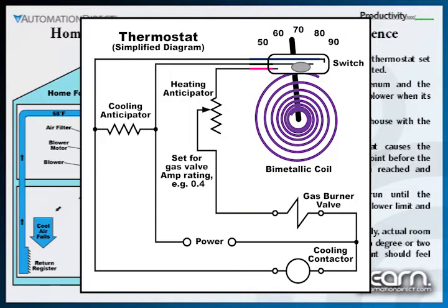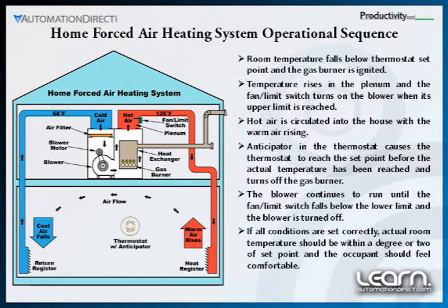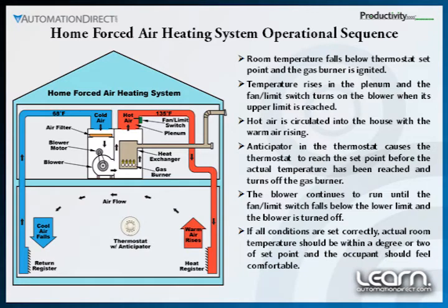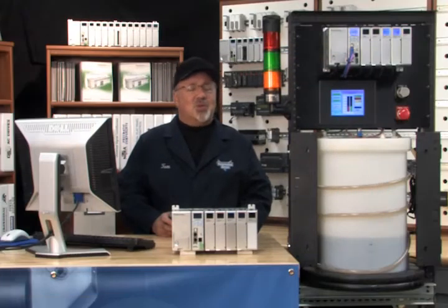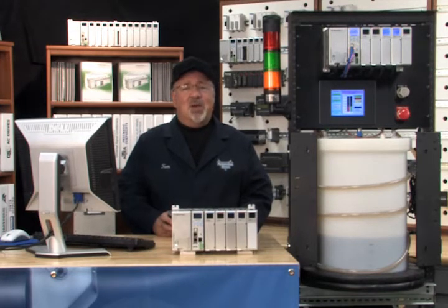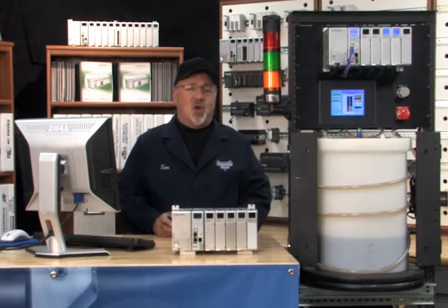The wire produces heat and causes the bimetallic coil to operate the mercury switch sooner, signaling that it has reached the set point temperature prior to the actual room temperature being satisfied. The blower will continue to run, adding additional heated air to the home, and if all is set properly, the actual temperature felt in the home will be at or close to the set point. The limit part of the fan limit switch is a safety that will turn off the burner if the air in the plenum gets too high, usually indicating that the blower isn't working. Sometimes the cooling side of older style thermostats also includes a form of anticipator, although newer digital setback thermostats with quicker response and accuracy have done away with wired anticipators, being replaced by smart programmable electronic setback thermostats.